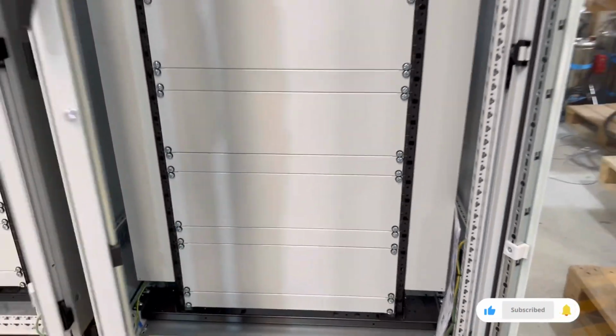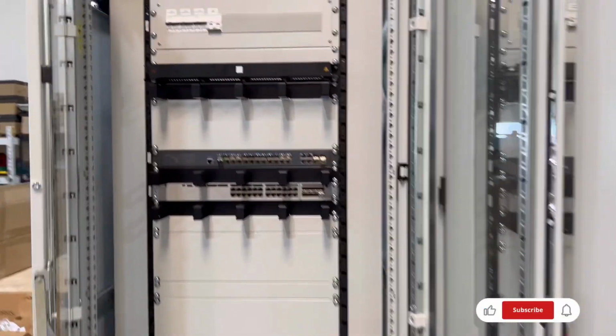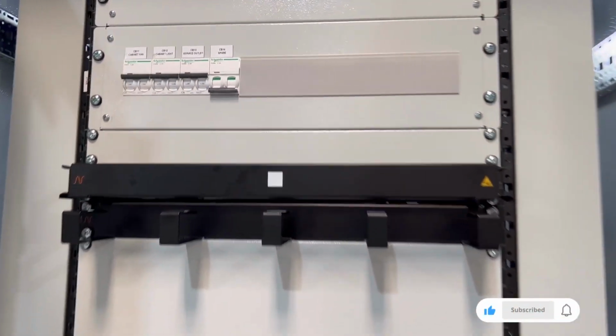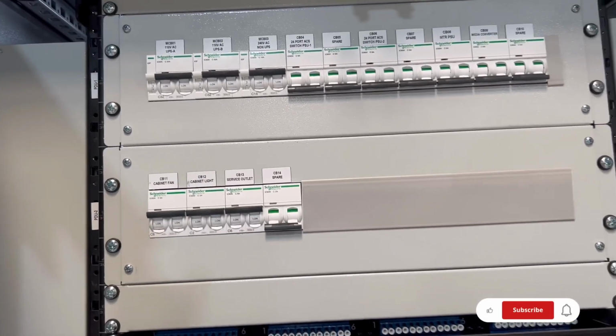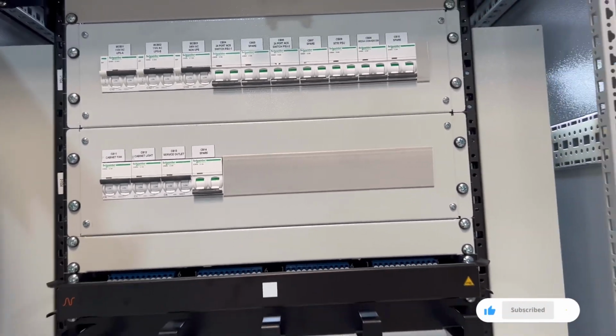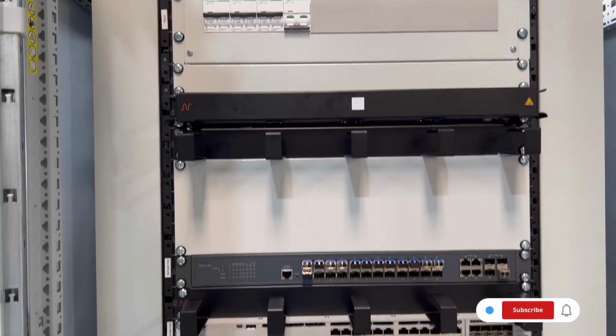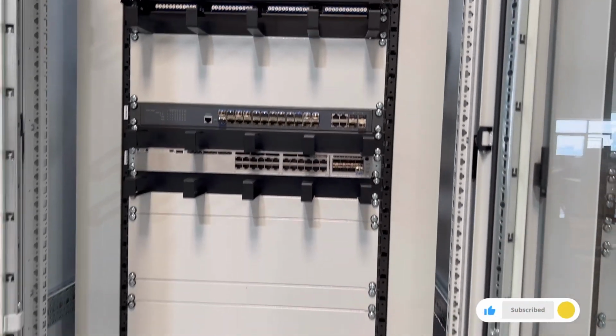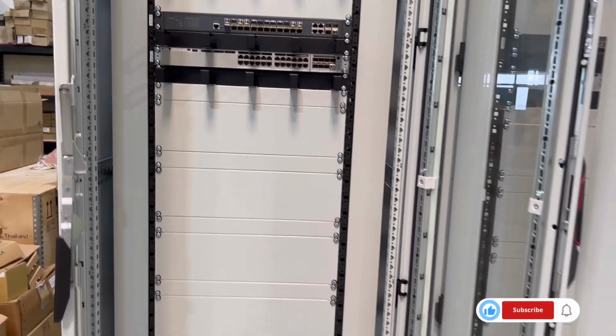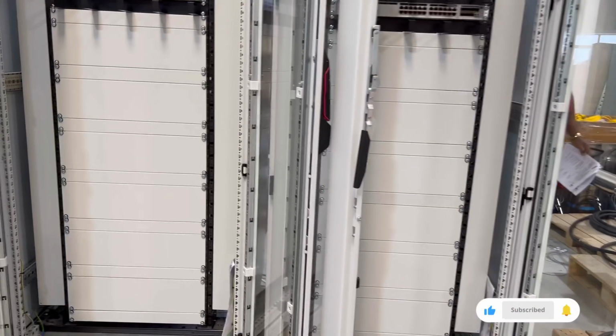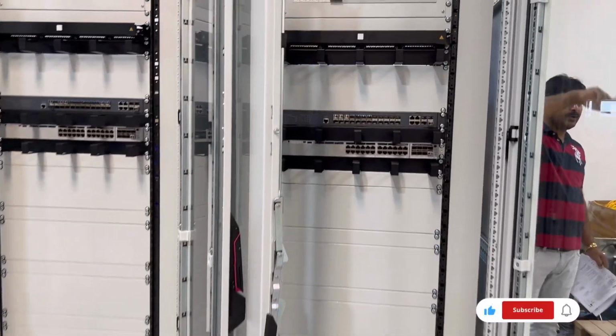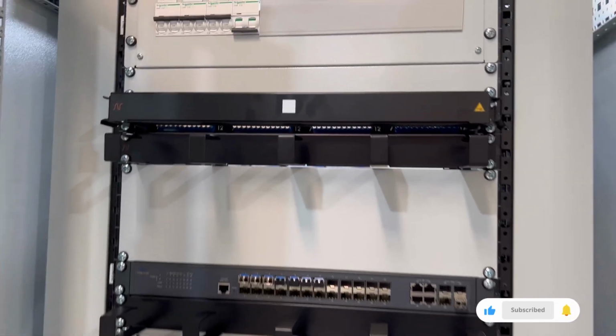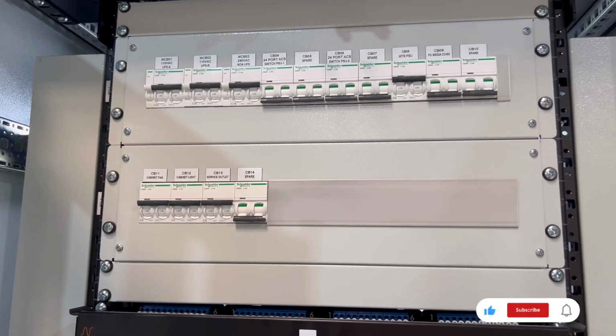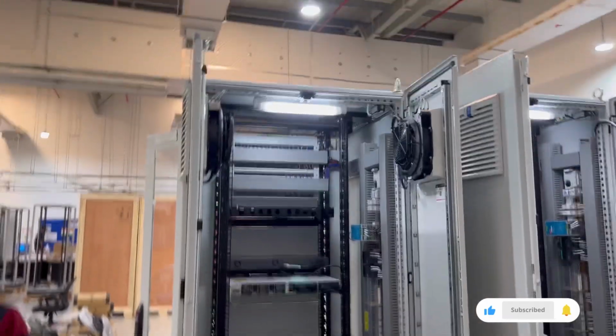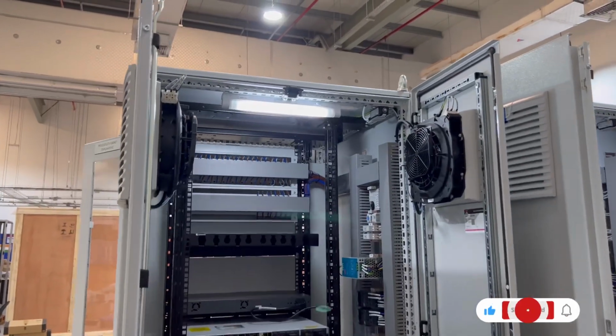points. So you check the panel, the cabinet, the tag, if all is correct, the breaker itself, all the devices are there, the screw, the earthing, wiring, so verifications of interconnections, drawing. That is the most important, the general assembly drawing. Meaning when you verify the general assembly drawing, you can easily identify what is missing. After that, you check your interconnection drawing.